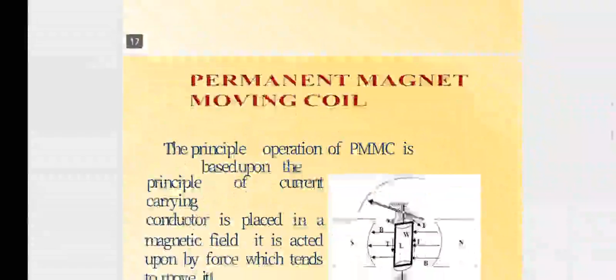Then moving coil instrument. There are two types of moving coil instrument, namely the permanent magnet moving coil instrument, which can only be used for direct current and voltage measurement, and the dynamometer type, which can be used for either direct or alternating current and voltage measurement. So moving coil instruments are subdivided into two: one for direct current, DC measurement, and the other for AC measurement.